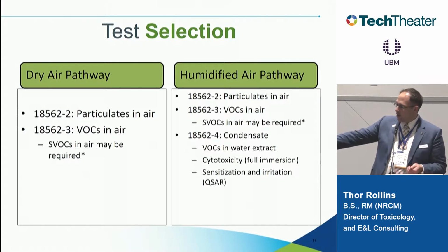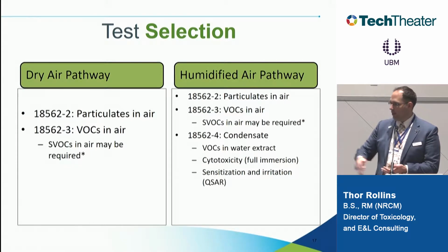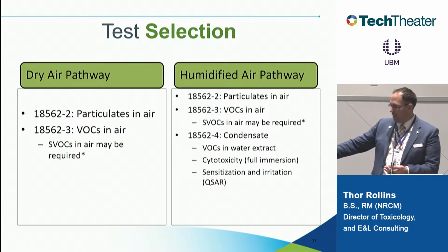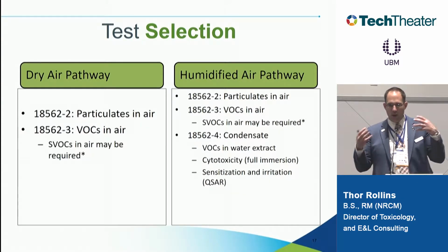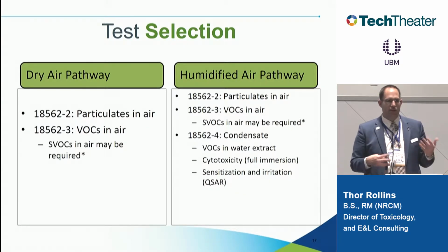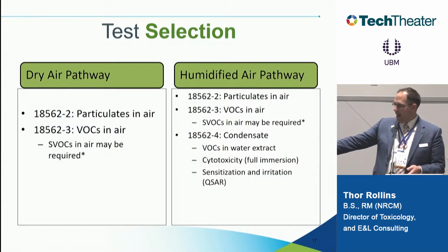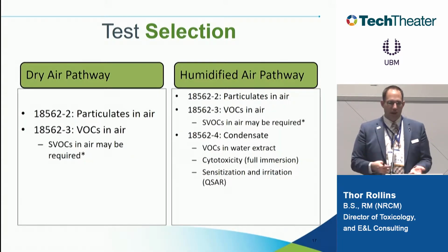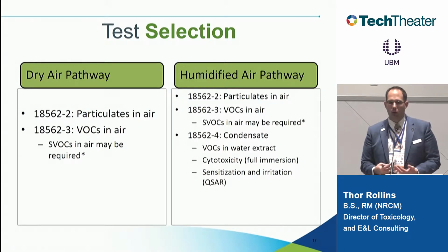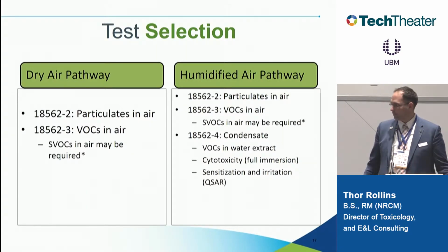Now your humidified air path, if you have humidity in that air, we have to do a little bit more. We still have to do particulates. We still have to look at VOCs. SVOCs in air may be required because, remember, water, if it's humidified, may be drawing out more than just the volatiles. It could be drawing off some semi-volatile compounds. Also, we now have to look at the condensate issues. Is that water drawing off different compounds in the air? So now we have to do some more traditional extractable and leachable tests in water to be able to determine the true impact of the safety of that medical device.